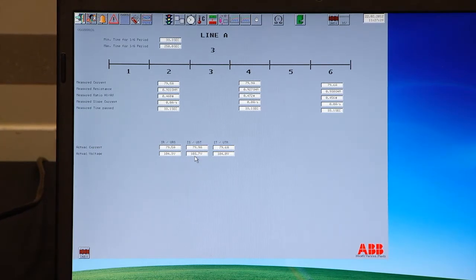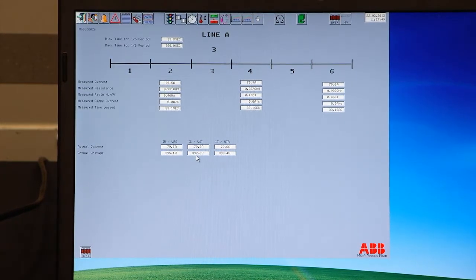So at 5 millihertz and at 400 and some volts, it draws 79 amps. So it takes 79 amps to saturate that core. Correct. 79 amps to saturate it, 400 volt to push it through. Yep. And that is of course going up and down a little bit. Initially you will see some 50 amps before the saturation comes. When the saturation comes it goes up to 80 amps or 79 amps.